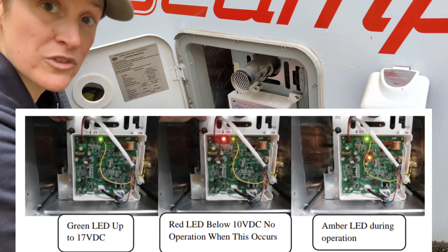So that would be the next thing I would check, is to make sure I have enough propane in my propane tank. And lastly, if all of those things were checking out, I would check the circuit board on the water heater itself. This part comes off and there's a circuit board behind it. And if the circuit board is working, there'll be a little green light that's on, and that'll tell you if that's working or if something has gone wrong with the circuitry. So that would be the last thing I check. I don't like to open this up. I like to keep it clean, keep it dust free. So if that's a problem, you can pop this open and there'll be a little green light, and that'll tell you if it's a circuit board or not. So those are the steps that I would take in that order to troubleshoot my water heater.